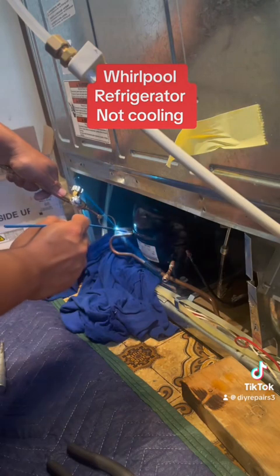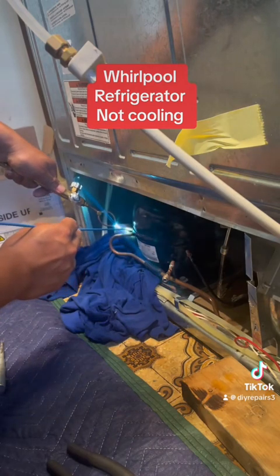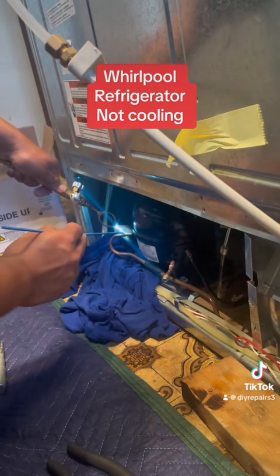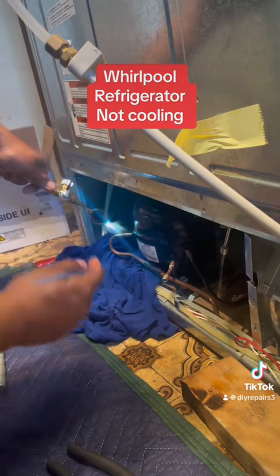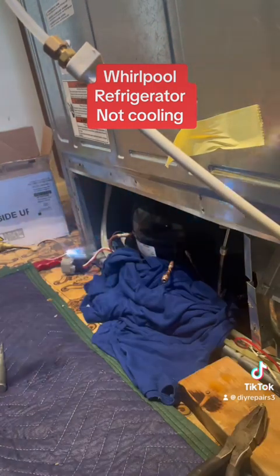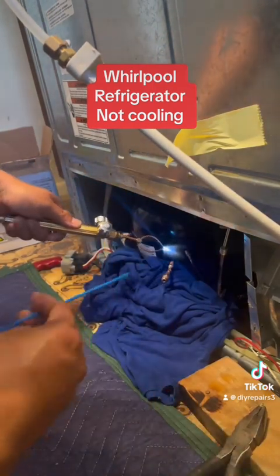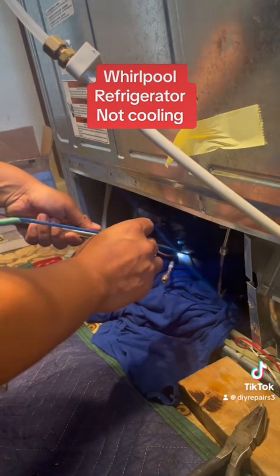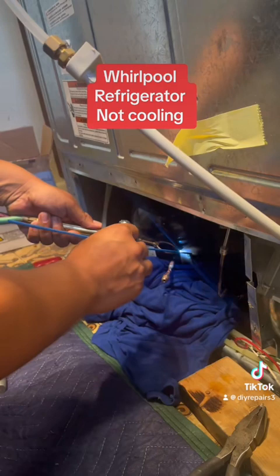That is the new compressor in. I'm going to go ahead and do the connections — go ahead and braze the connections. What helps me do this pretty fast is sanding the connection. Make sure you sand the connection. See, that one's finished — I'm gonna go ahead and do the next one. Make sure you don't have any leaks.